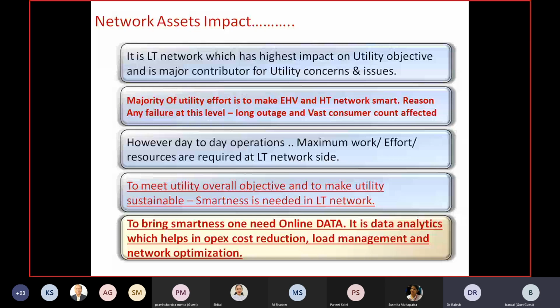Today I have more than 3,000 people maintaining the LT network, and just 400 people maintaining the EHV network, yet power flows through both. The majority of utilities put effort and technology into the EHV and HT network. The biggest reason is that if there's an outage at the HT or EHV level, those outages are long in nature and a large number of consumers get affected. In our case, if one grid gets affected, almost 25,000 consumers are impacted. If one HT feeder gets affected, around 2,000 consumers are impacted.